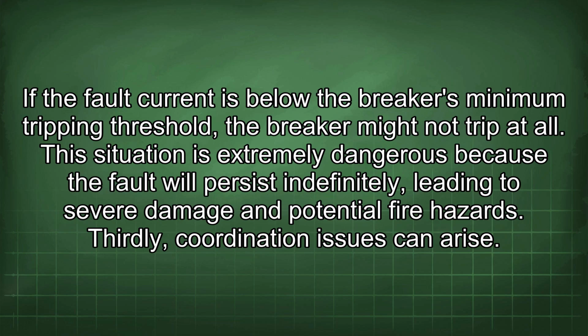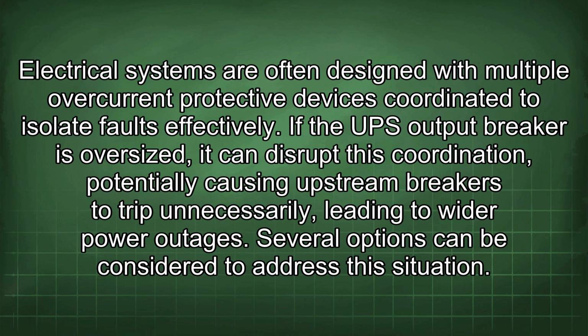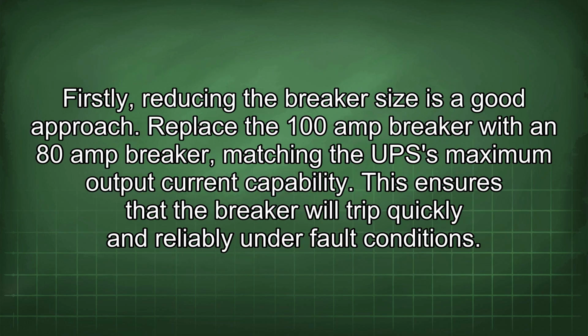Thirdly, coordination issues can arise. Electrical systems are often designed with multiple overcurrent protective devices coordinated to isolate faults effectively. If the UPS output breaker is oversized, it can disrupt this coordination, potentially causing upstream breakers to trip unnecessarily, leading to wider power outages. Several options can be considered to address this situation. Firstly, reducing the breaker size is a good approach. Replace the 100 amp breaker with an 80 amp breaker, matching the UPS maximum output current capability. This ensures that the breaker will trip quickly and reliably under fault conditions.